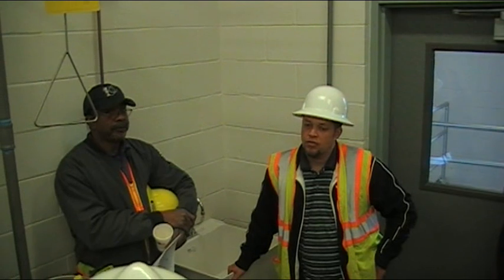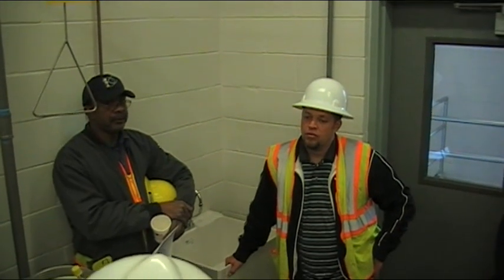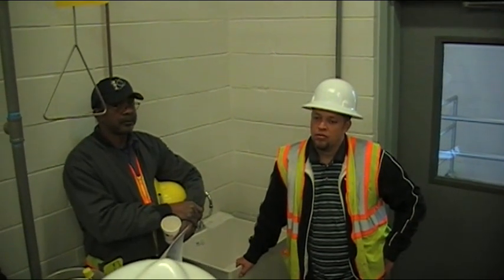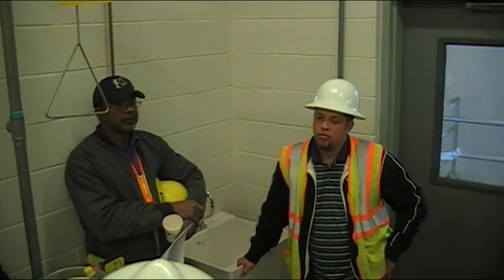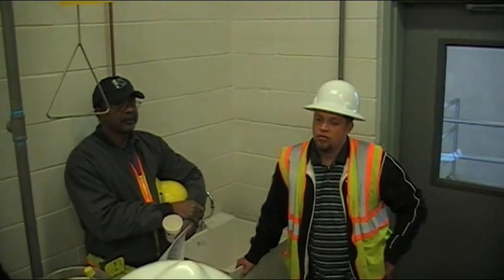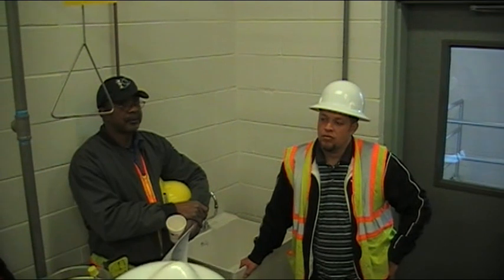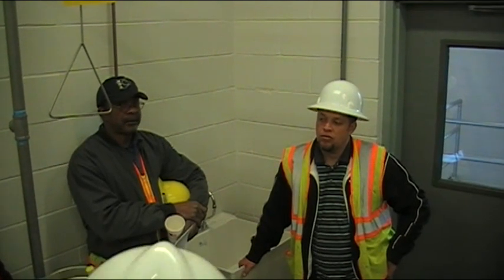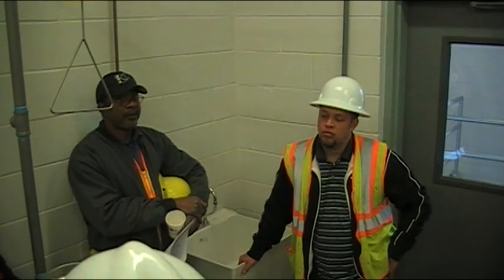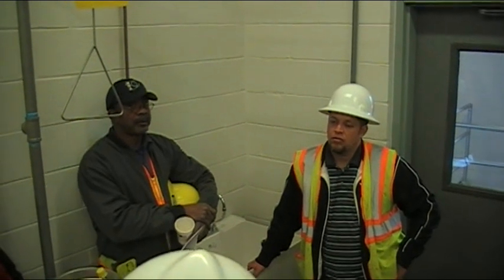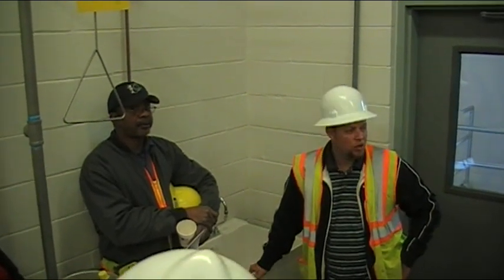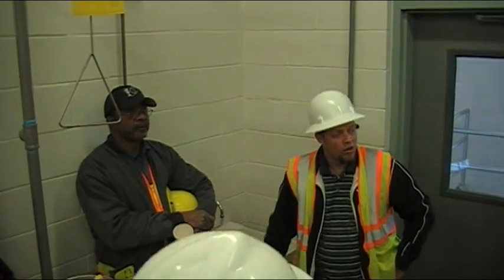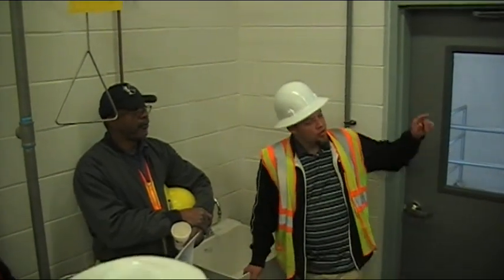If it's in automatic, the SCADA is telling it to start. When power comes back, since it's all relay logic, if that contact is closed, the unit's going to try to run. If everything is in hand and you lose power, when you get power back up, everything's going to start running again. Y'all understand that? Power glitch comes back on, is SCADA still telling it? Basically what he's saying, right, that is correct.